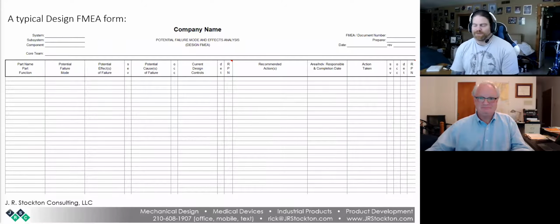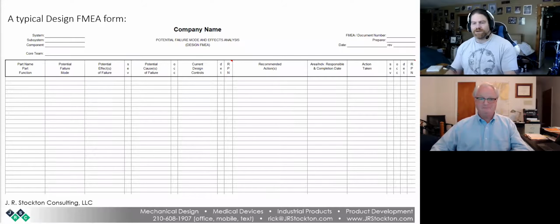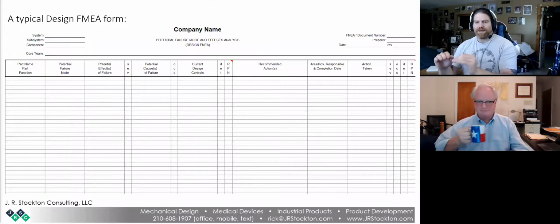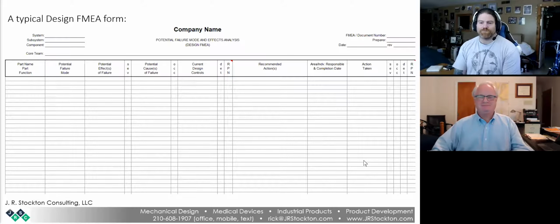And I'm not saying Band-Aids are necessarily class one, or necessarily exempt, depending on the pathway and what the indications are and everything. You could have a class two, or you could have a 510K or not have a 510K. We won't go there. I'm just saying that if you take what everybody believes is state of the art, this is the worst thing that is likely to happen with this category of devices, and you set that as the worst score that you should have on RPN. If you see a bunch of RPNs higher than that, you should be questioning that in the design process, and in your risk management meeting.